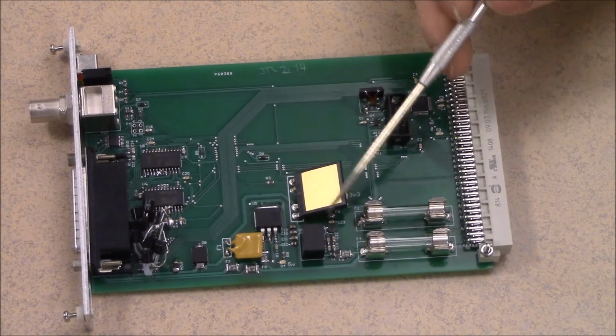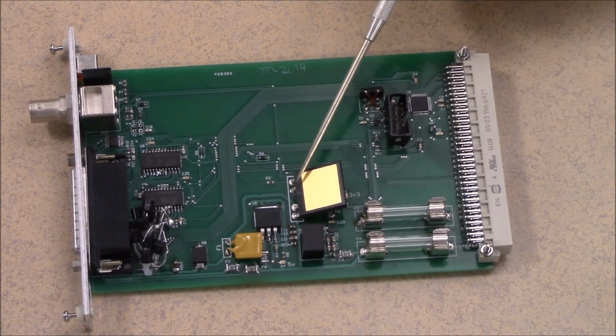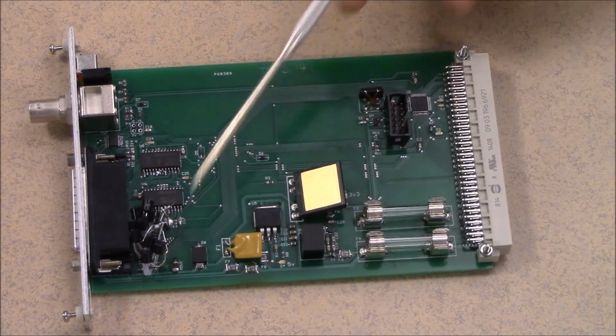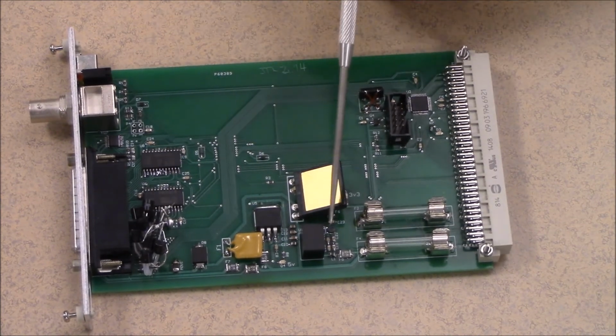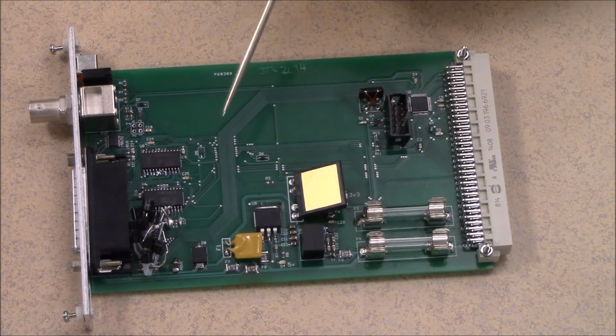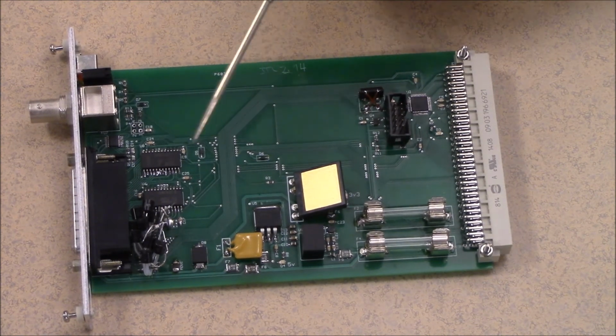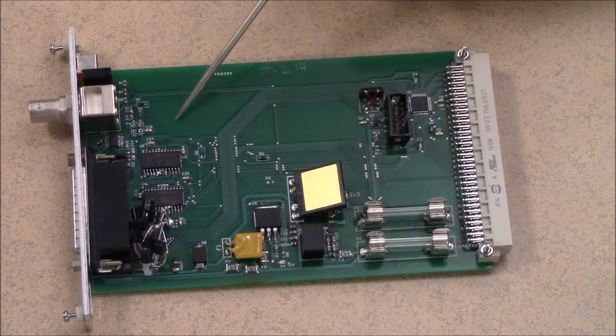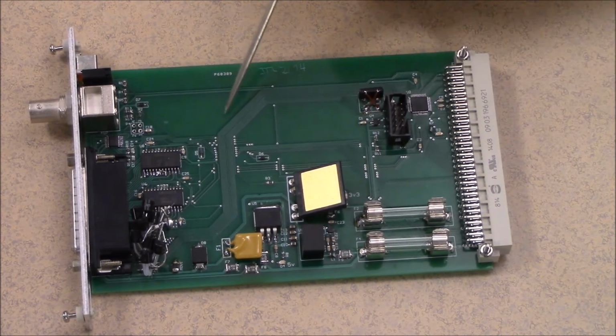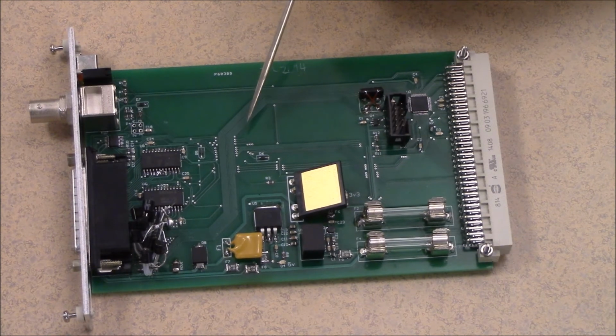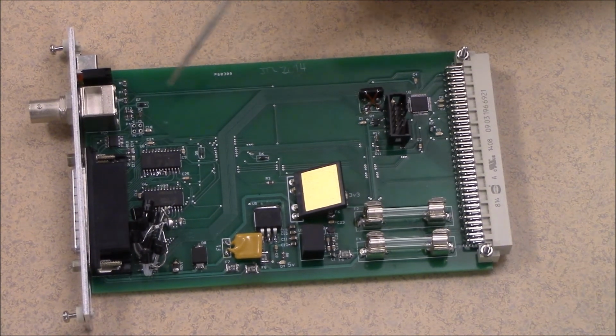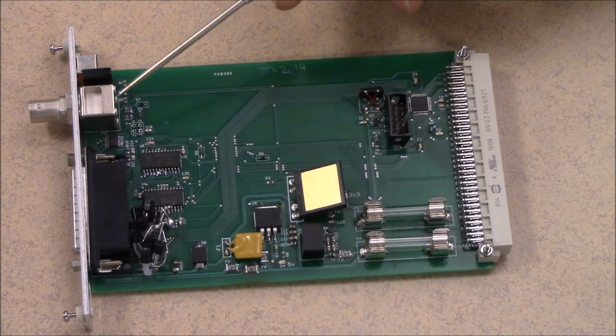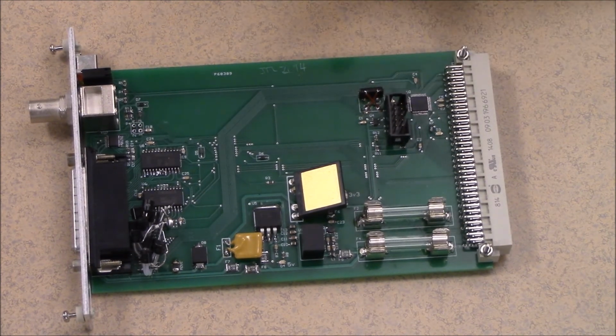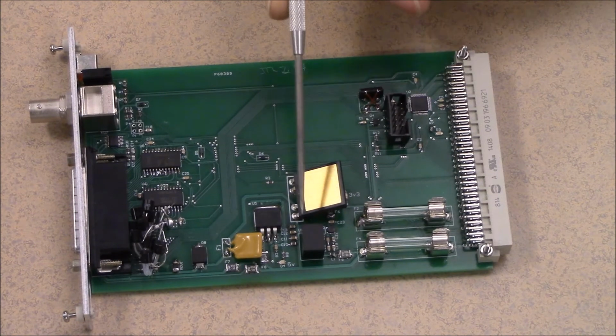This device with a yellow back here is a DC solid-state relay, which is used to switch the switched 24 bus. The switched 24 bus has to be far more robust than originally expected, not only because of the many relay loads switched upon it, but our greatest load in the entire device, and actually what determines the rating of the chassis power supply, is the fan that we use to cool the water-cooled load, which is an extremely powerful fan and pulls 2 amps at maximum throttle, which is part of the reason why we like to throttle it down when that is unnecessary. It also saves our hearing.